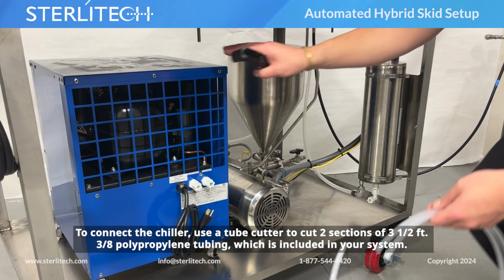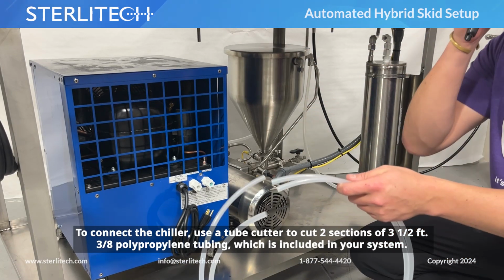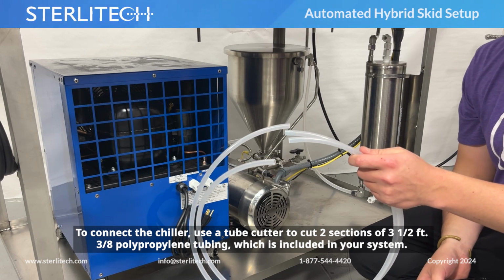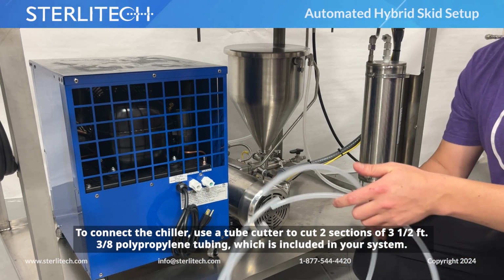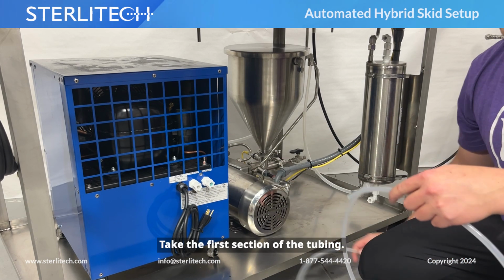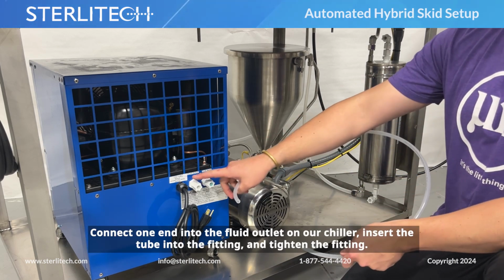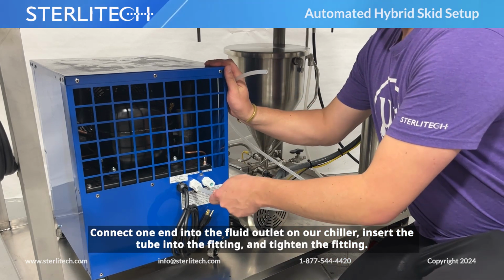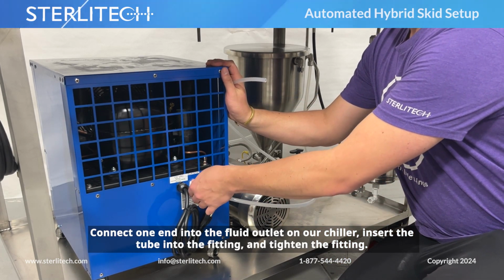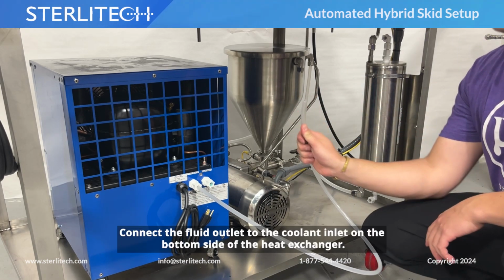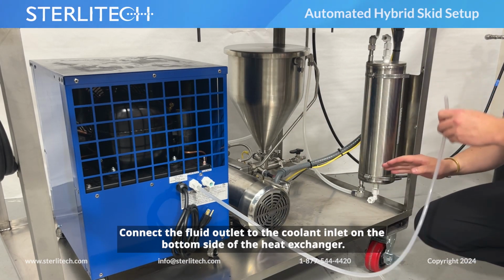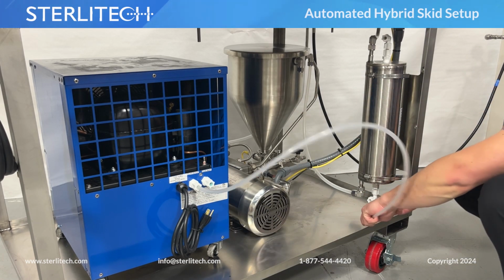To connect the chiller, use a tube cutter to cut 2 sections of 3.5-foot 3/8 polypropylene tubing, which is included in your system. Take the first section of the tubing, connect one end into the fluid outlet on our chiller, insert the tube into the fitting, and tighten the fitting. Connect the fluid outlet to the coolant inlet on the bottom side of the heat exchanger.